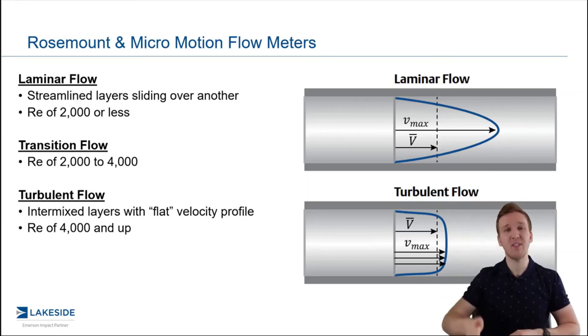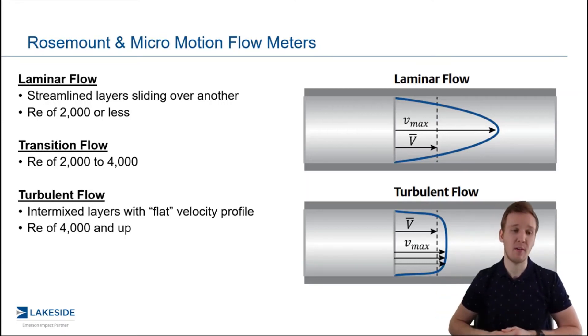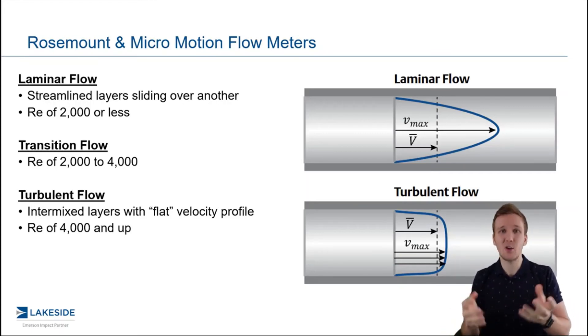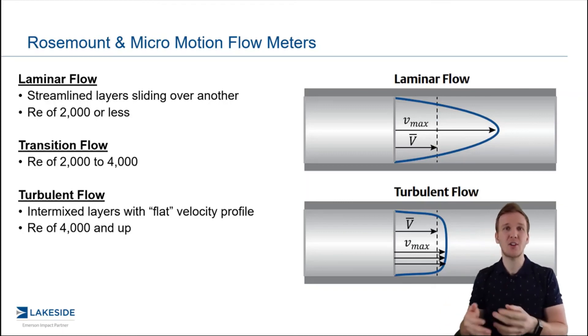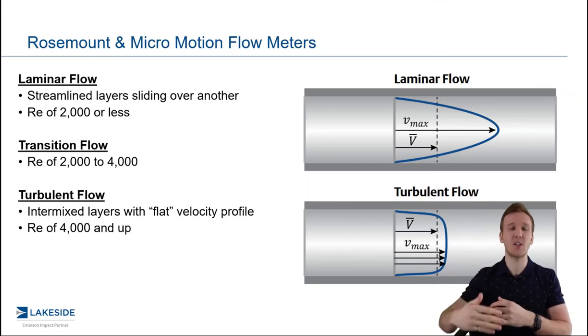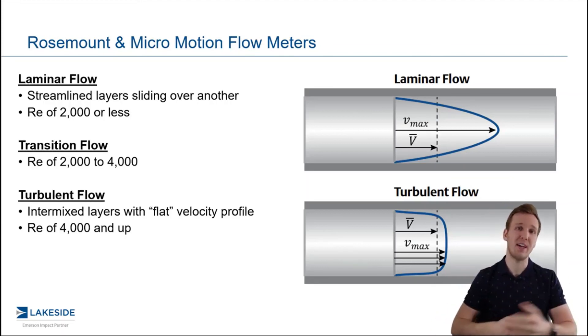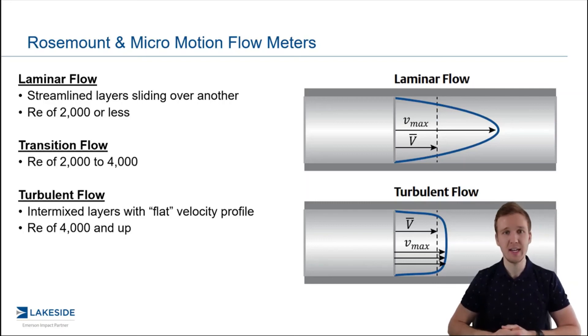And that's what we want — a flat, nice and even velocity profile. The reason for this is because a lot of volumetric flow meters are really measuring the velocity. So if we're measuring velocity, we want to make sure that wherever we're measuring it across this pipe — whether it's the average or at different points — we want to make sure that it's reflective and well-representative of the actual velocity in our flow meters.